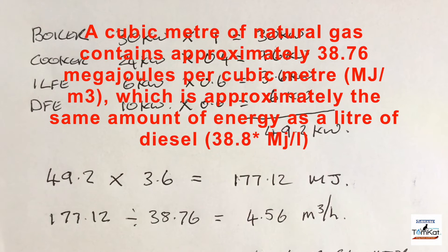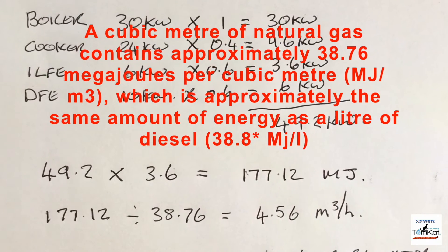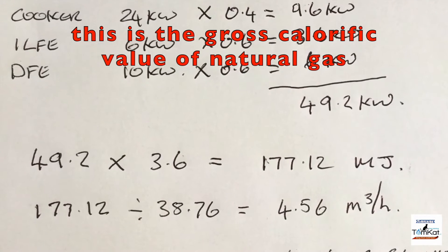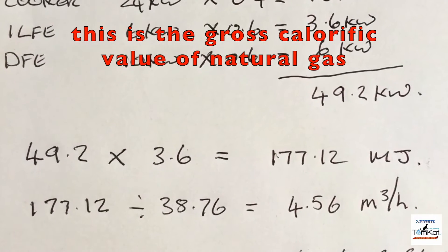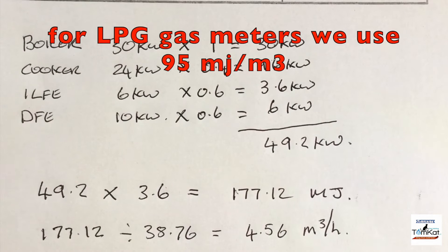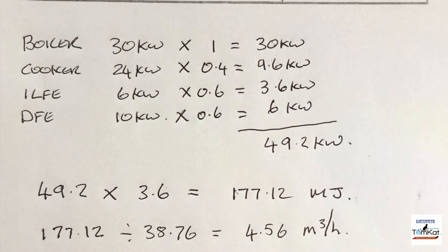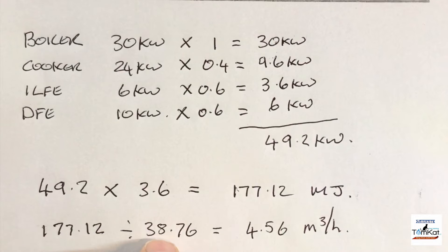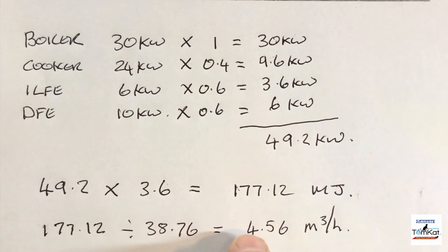Step three: divide the total number of megajoules by the calorific value of natural gas — currently 38.76 — to determine the equivalent gas flow rate in meters cubed per hour, which will determine the meter size required. So 177.12 ÷ 38.76 = 4.56 meters cubed per hour.